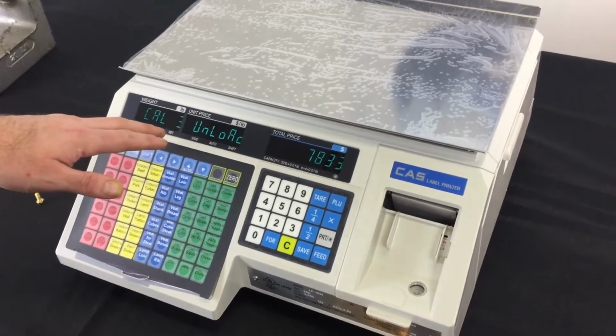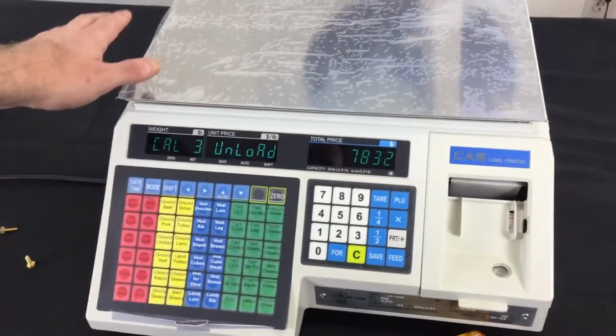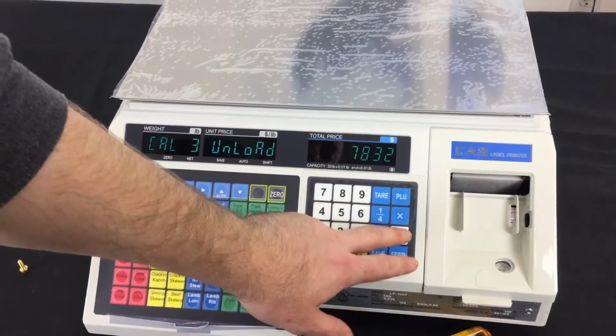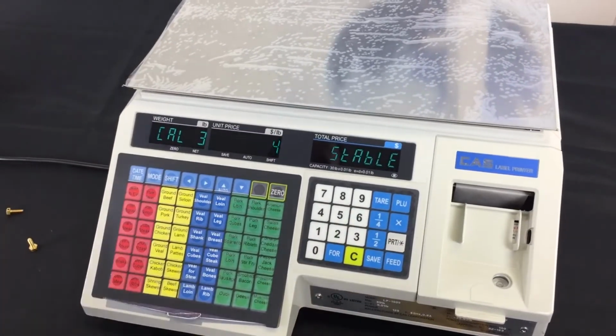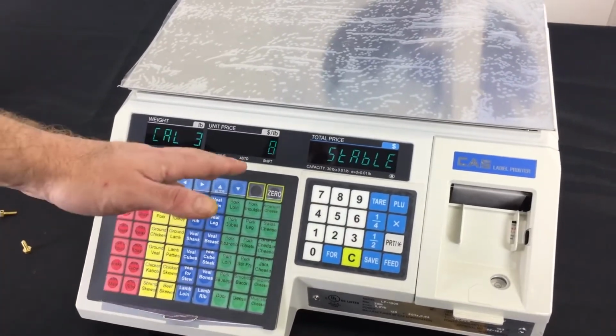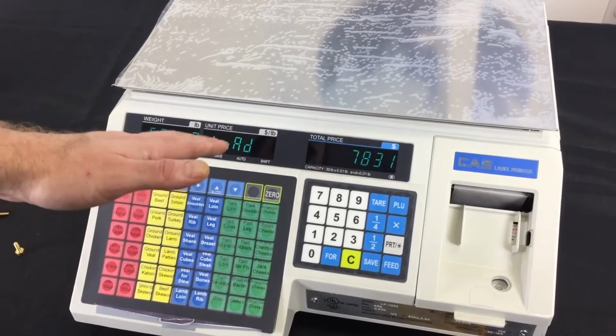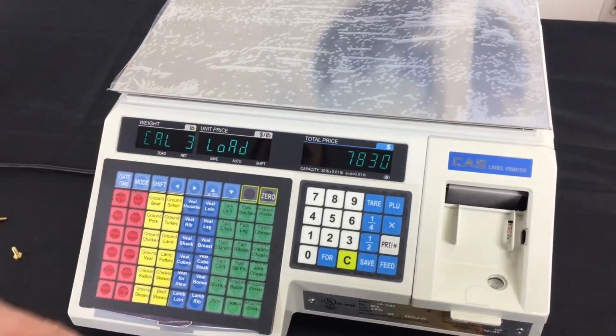It will say unload on the top of the scale. So now with no weight on the platter, you want to make sure you just press the print key in order to do your 0 calibration. Now it'll count up. After it stabilizes, it'll go to load. Now that we're at load, we're ready to calibrate.